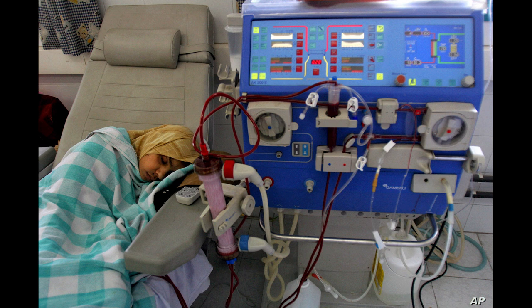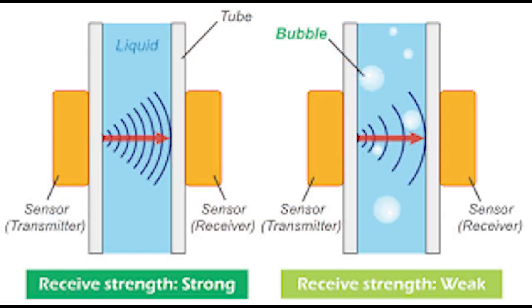Ultrasonic sensors are found in most medical devices that handle liquids, especially devices that handle patient infused liquids. These sensors tell the internal computer when the fluid starts, when it stops, or when there's an anomaly like an air bubble that's traveling up the hose.